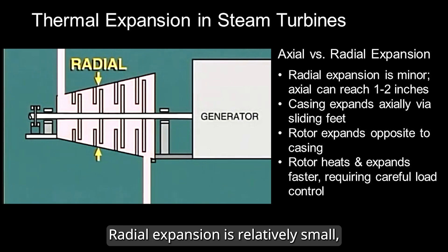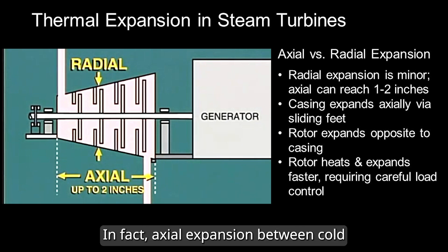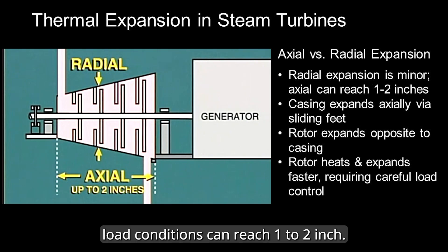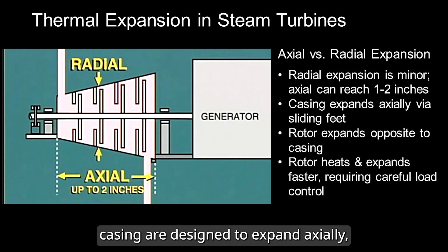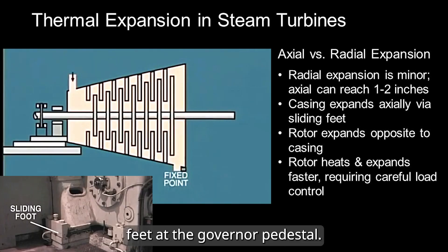Radial expansion is relatively small, but axial expansion is much more significant. In fact, axial expansion between cold and full load conditions can reach 1 to 2 inches. To accommodate this, turbine casings are designed to expand axially, often using sliding feet at the governor pedestal.